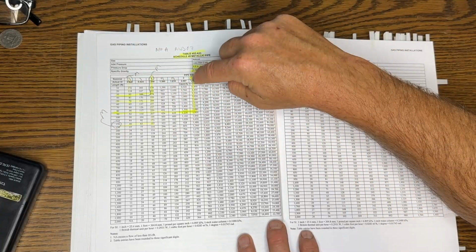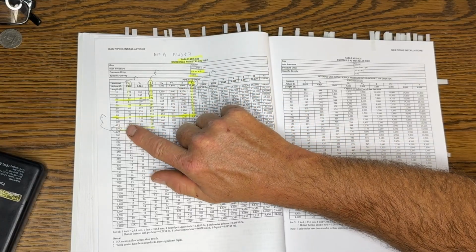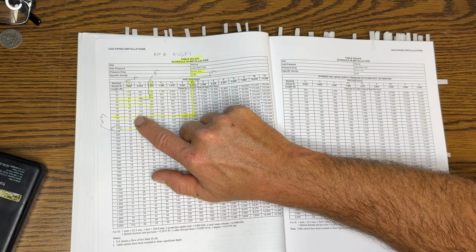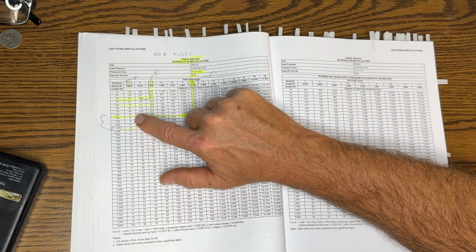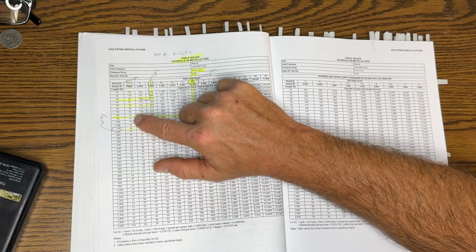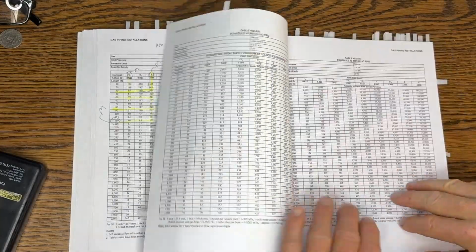Now the ones I've circled, those are the actual answers. So if I was given, let's say, my length is 90 feet and my delivery I had to do was like 50, what size pipe do I need? Well, there's 52 there at 90, and it would be half inch diameter for your Schedule 40. So that's how you look that up. All right, let me keep on trucking through here.